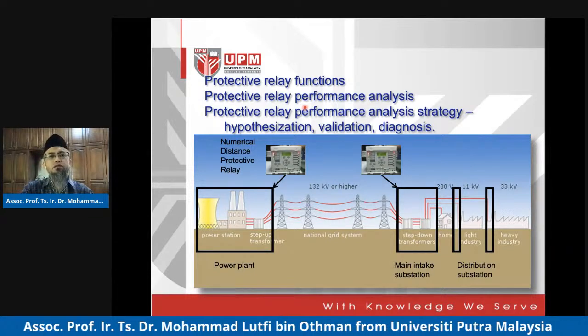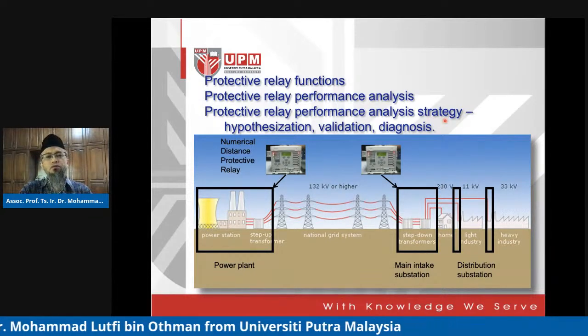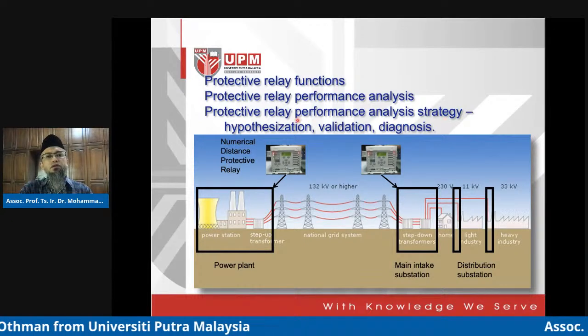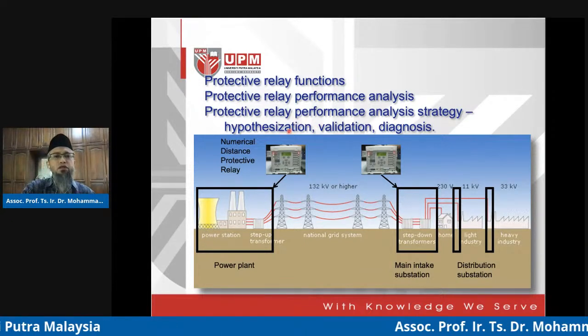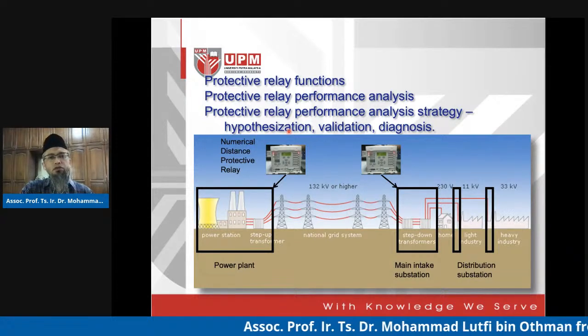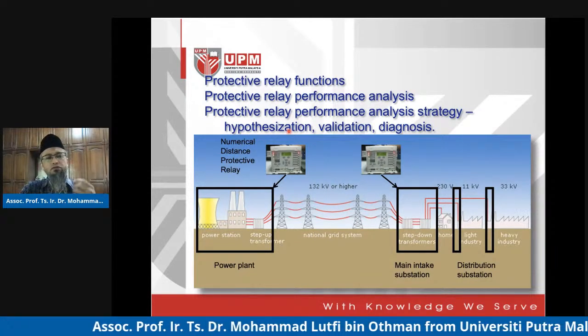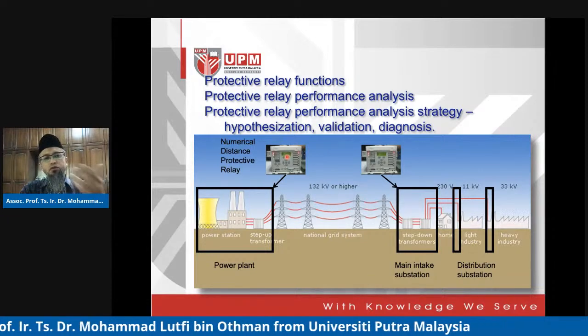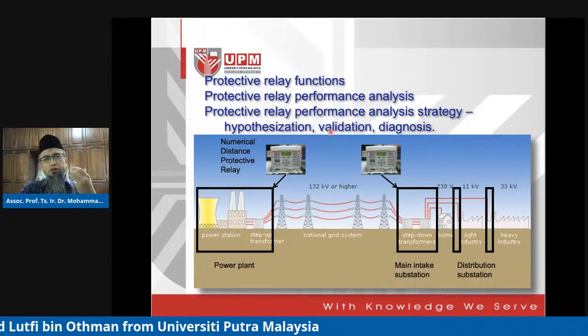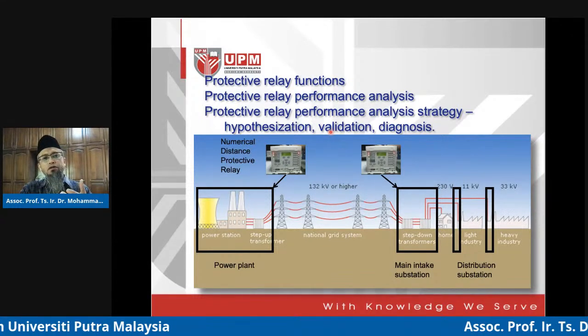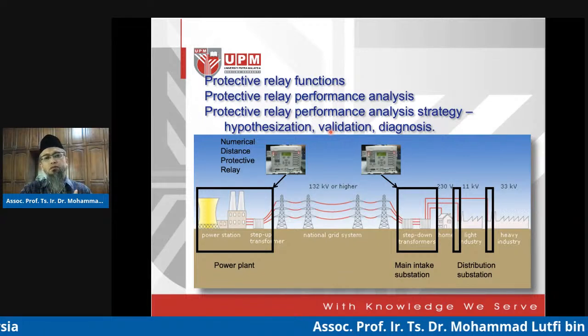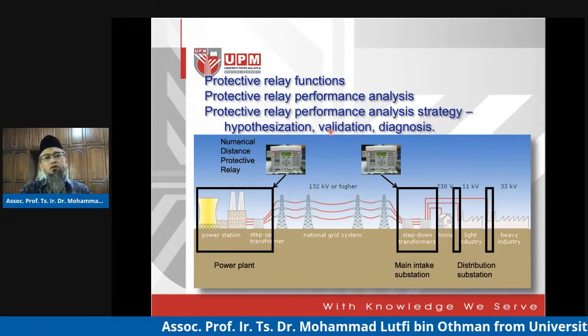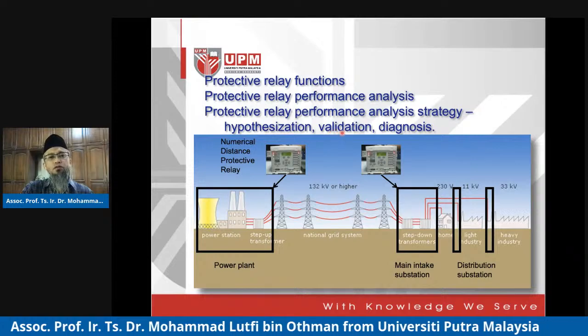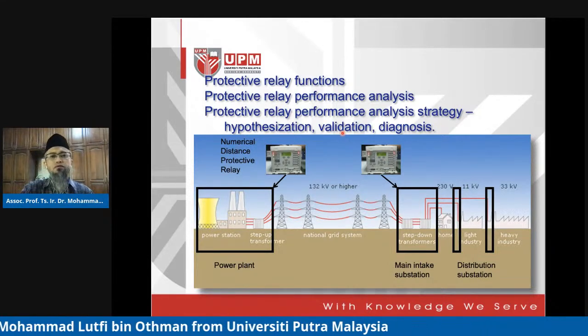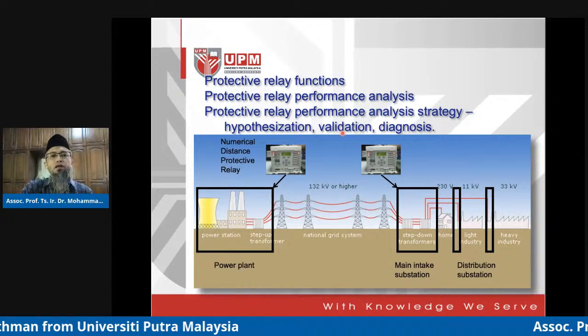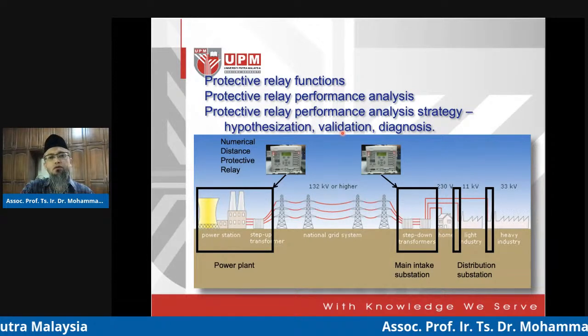To do that, there's a particular strategy involving three steps. First, hypothesize: extract knowledge from the protective relay of interest whose performance we're going to analyze. Once we have the knowledge, the algorithm—in our case, prediction rules or decision rules of the relay's behavior—next we validate, using the rules to validate the performance of other, unknown relays, to see whether they are operating correctly or otherwise.